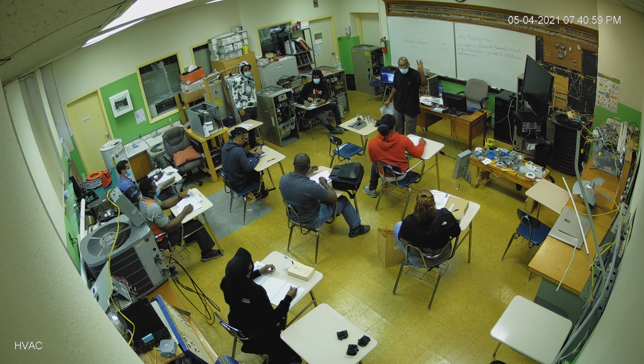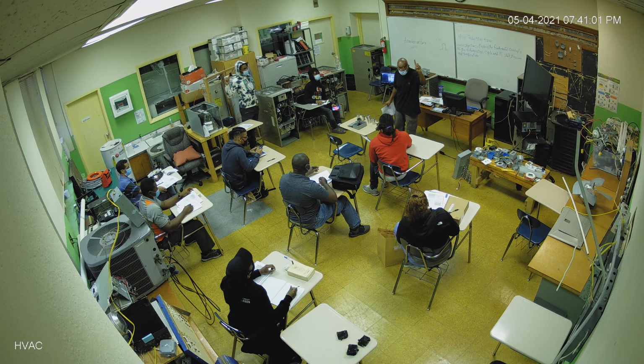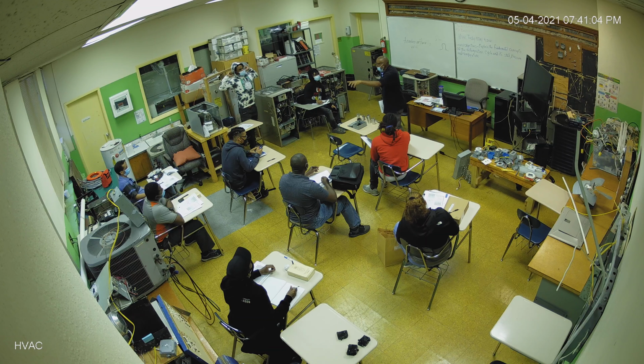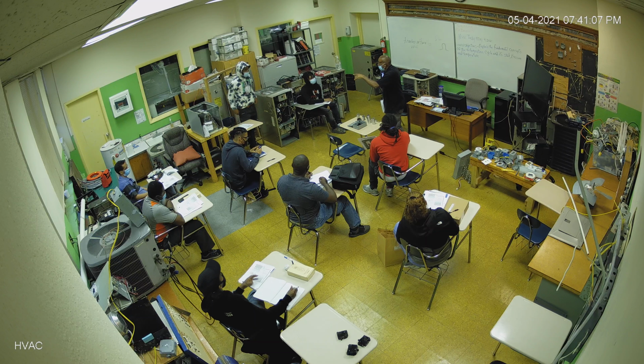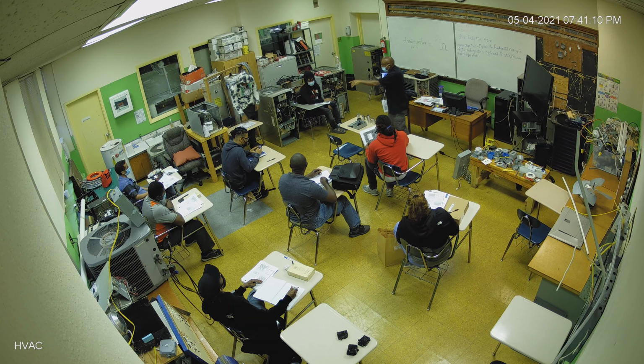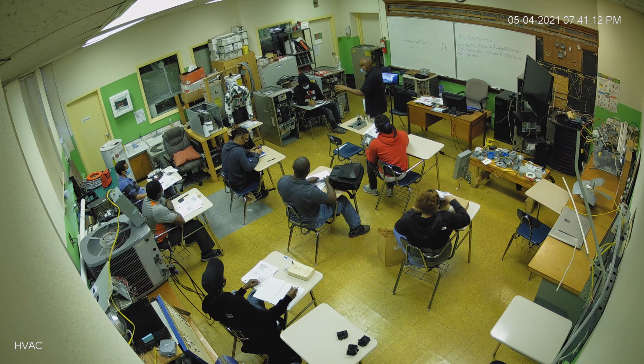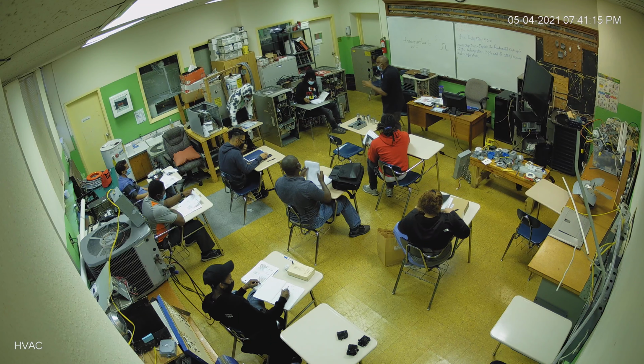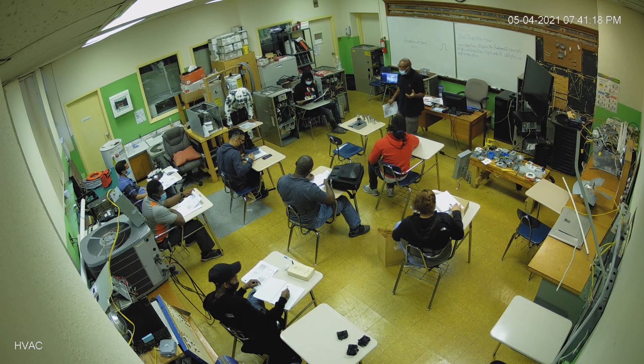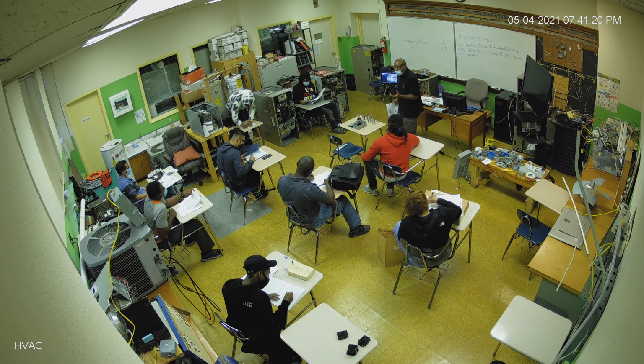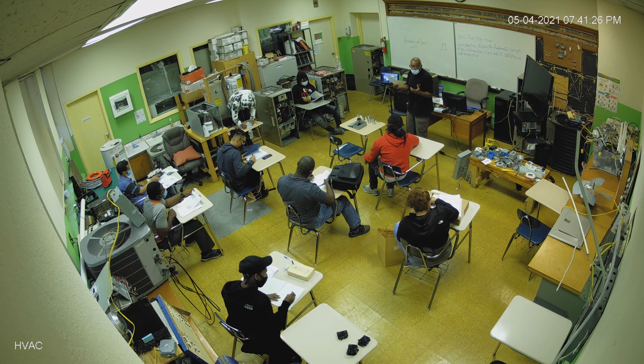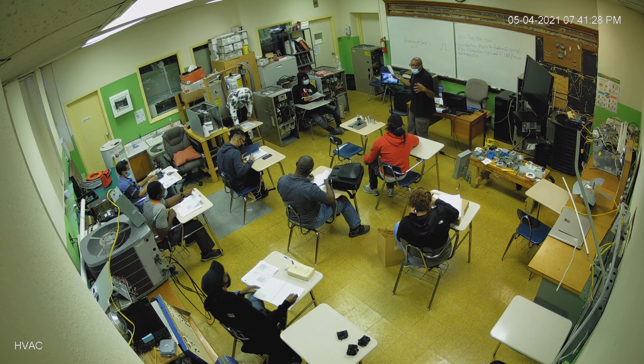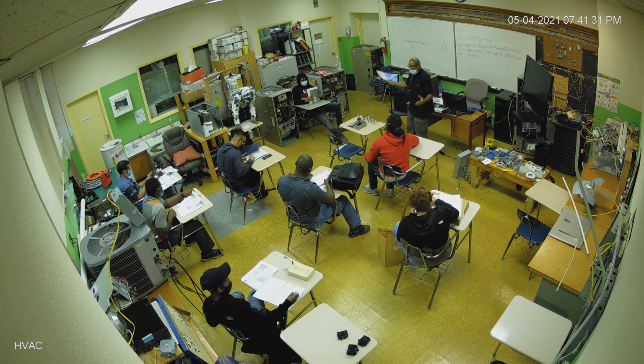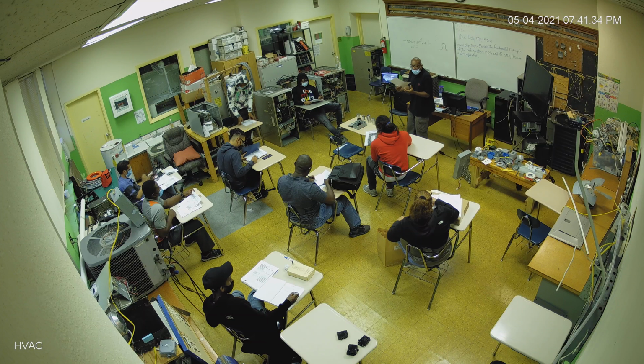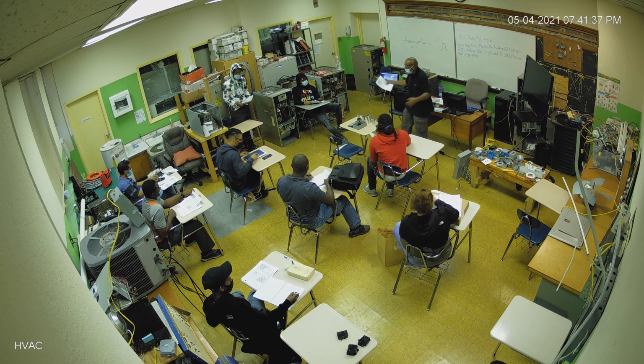What are the 3 again on your capacitor? Fan, herm, and common. And HERM stands for what? Write it in your notes - do you have a composition book? Bring one next week, please. HERM stands for compressor, hermetic - that's what the word HERM means. Hermetic is a word that means sealed, and sealed is just the idea of the compressor because they're sealed, it's not open. You see how this is open here?